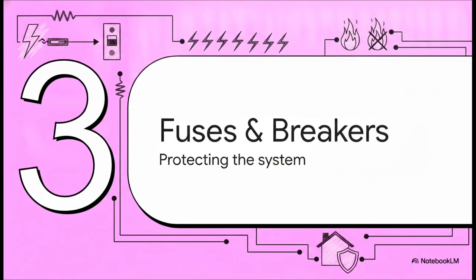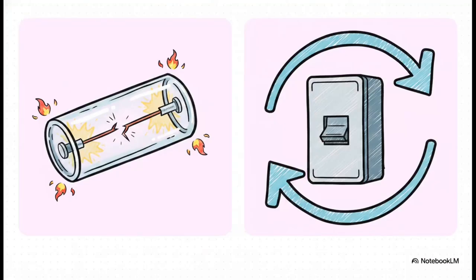That brings us to Section 3, fuses and circuit breakers, protecting the system. These guys, fuses and circuit breakers, they're basically your system's frontline defenders. Their whole job is to open the circuit before the wires can overheat, burn, or just fail violently. Now, a fuse is a one-time overcurrent device. When the current exceeds its rating, a tiny metal element inside physically melts, permanently breaking the circuit.